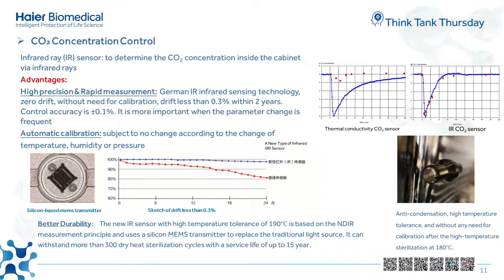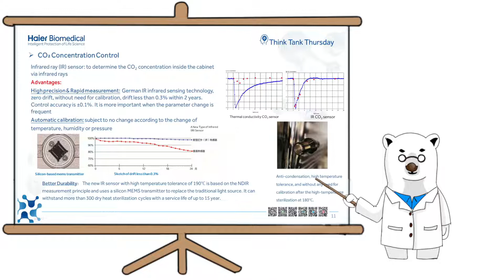And some competitors use thermal conductivity CO2 sensors, which are not ideally correlated with the actual reading. Besides, the high temperature tolerance of 190 Celsius degrees enables the adoption of 180 Celsius degree dry heat sterilization methodology in contamination control, which is also critical for a lot of researchers.